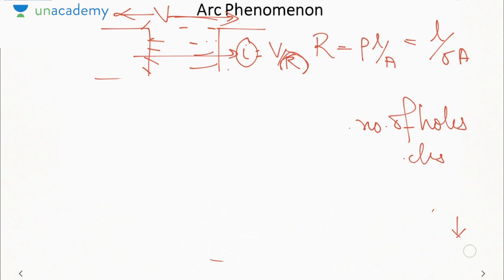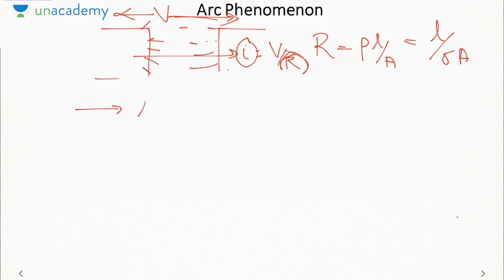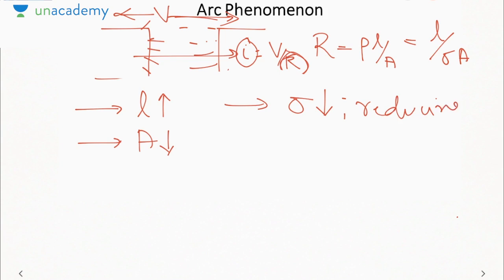From the formula, what I can say, to extinct the arc, we need to increase the arc resistance, which can be done by increasing the length of the arc, reducing the cross-sectional area of the arc, or by reducing conductivity, or reducing the number of charged particles, that is N.